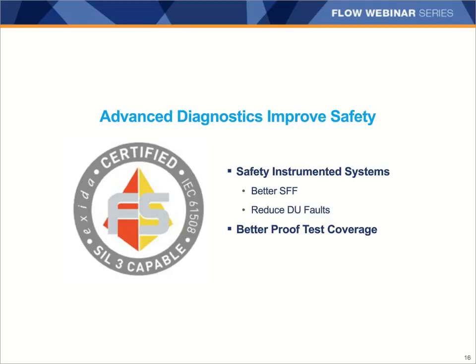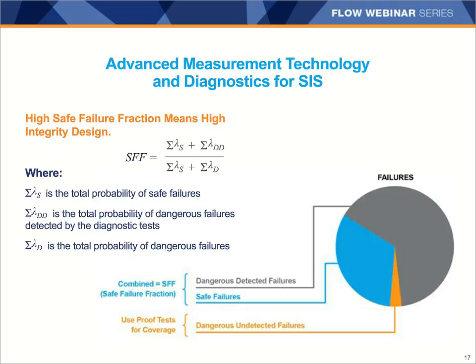So I'm not going to get into a lot of the math here, but let's take a quick look at how to calculate safe failure fraction and how diagnostics can help improve that score. The total failures in time, or FITs, are made up of both safe and dangerous failures. For a safety application, we're more concerned about the dangerous failures. The safe failures, whether they are detected or can't be detected, are defined as those that would result in a safe situation even in the event of a failure.